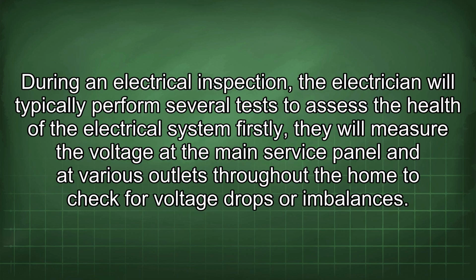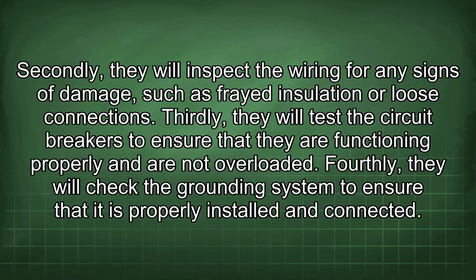During an electrical inspection, the electrician will typically perform several tests to assess the health of the electrical system. Firstly, they will measure the voltage at the main service panel and at various outlets throughout the home to check for voltage drops or imbalances. Secondly, they will inspect the wiring for any signs of damage, such as frayed insulation or loose connections.